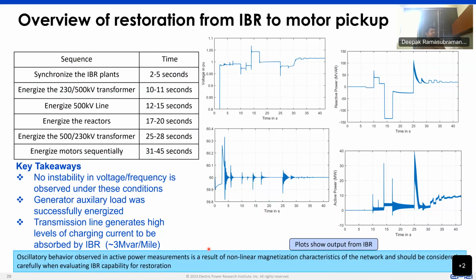You go all the way from first synchronizing the various inverter plants that are there, then pick up the transformers, pick up transmission lines, pick up reactors along the way to keep the voltage low, and then pick up motor load to be able to start the generator and then make the generator come online. But there is an impact of saturation. So some of the characteristics that we see here with respect to the oscillatory behavior are a result of the nonlinear magnetization characteristics of the network. And that is something that we have to evaluate or ascertain its impact when we are evaluating the restoration of the inverter.